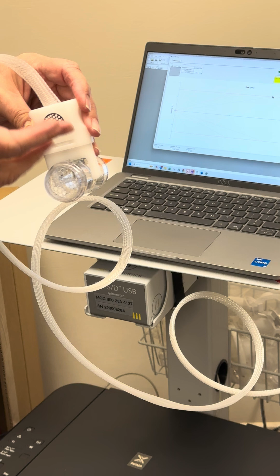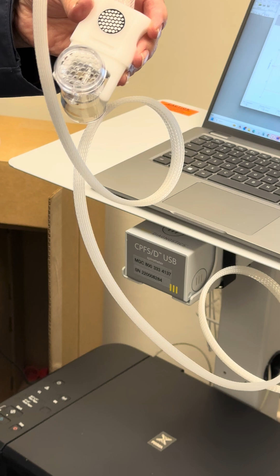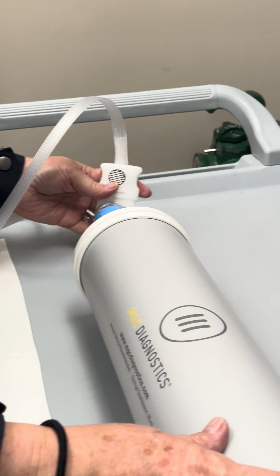this is constantly sampling up. It has a little bit of a vac pull on it, so that's how it's sampling the patient breath. So it does have the ability to pull water or fluid or whatever up in there. So I always like to keep the umbilical in the upright position even when I'm doing patient testing. So honeycomb to honeycomb, honeycomb to patient, because they're sweet like honey. Well, that's a good way to put it.